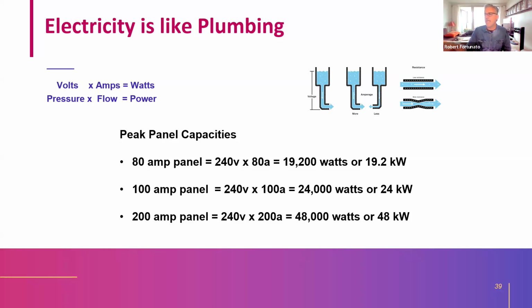But the number at the end is what I want you to focus on, because an 80 amp panel - the electricity coming into the house is at 240 volts from the utility, from Southern California Edison, for most people. And 240 volts times 80 amps is 19,200 watts, or 19.2 kilowatts.